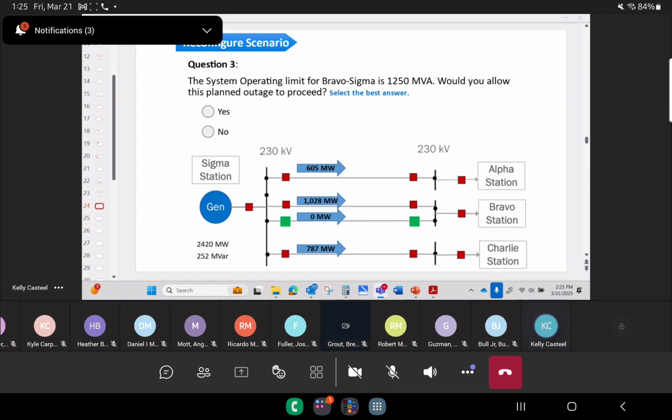I can give you an example of a time when I came really close to doing that. It was an early morning event, and we had more generation than we did load. We had pretty much everything regulated down that we could, and had a plant operator that did not want to comply with an operating instruction. They were ramping up because they were having some issues at the plant, and essentially the unit was probably going to trip if they didn't ramp up.